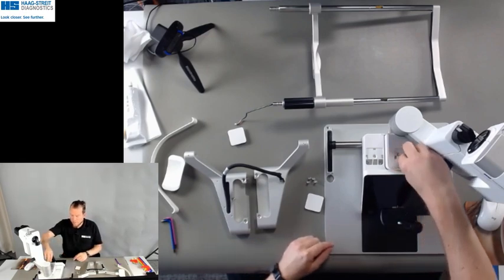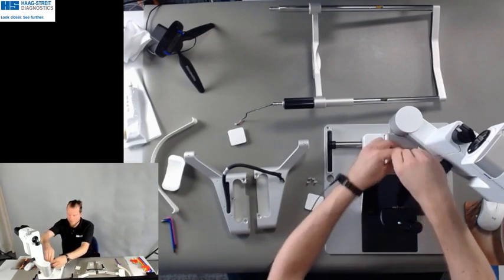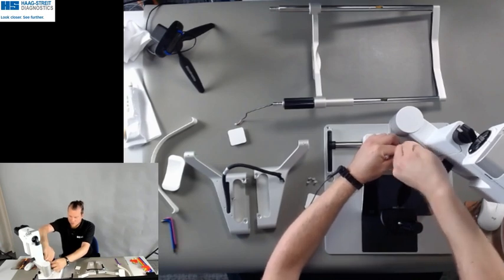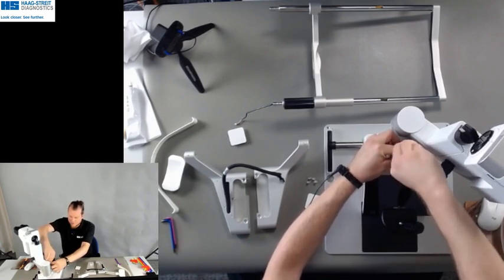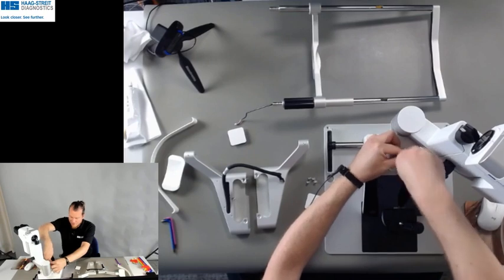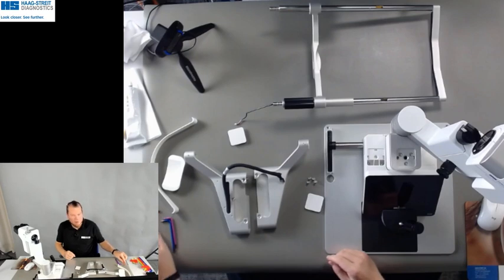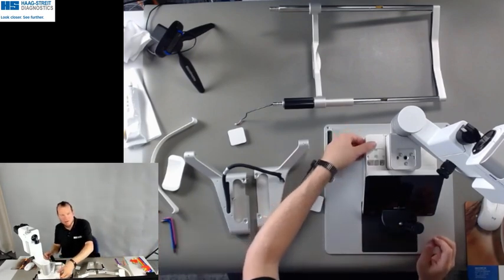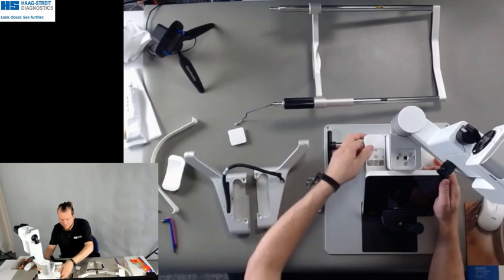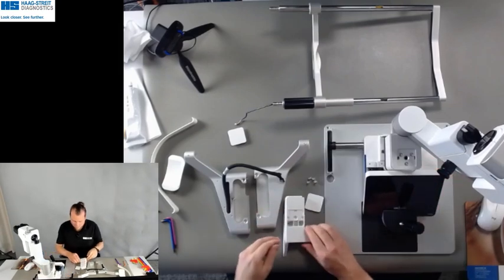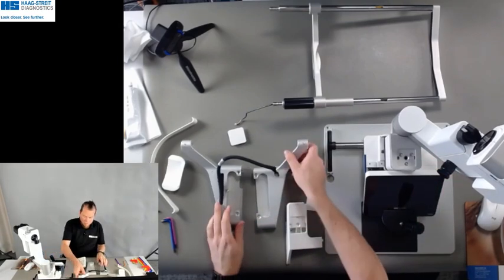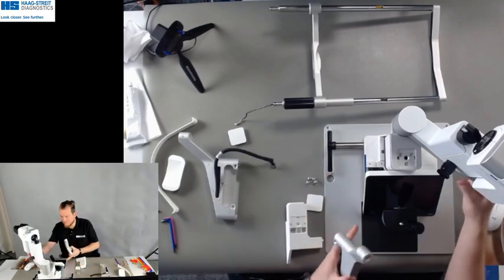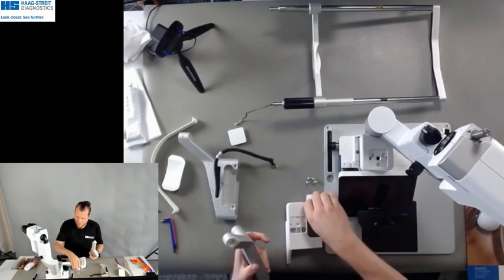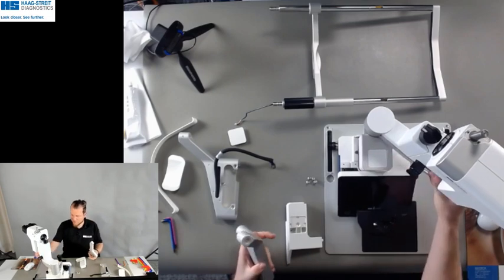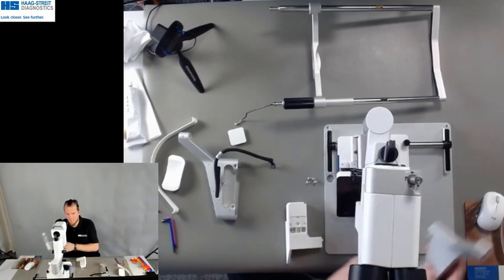With a Torx 10, you can move up the spindle. I would say do at least halfway. That's around, I would say, 10 rotations. So it's out of the end position. Then you can also remove this cover here on the side. We mount the first rail. This one here can be closed again, so you can move the tower out of the way.